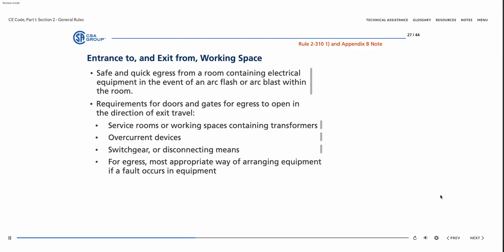The most appropriate way of arranging equipment is so that if a fault occurs in the equipment, the egress route from the room or space does not pass by the location of the fault in the electrical equipment. There is a need to provide two egress doors from the room or space, arranged in such a manner that a qualified worker would not have to pass by the fault location on the way to exit from the room.